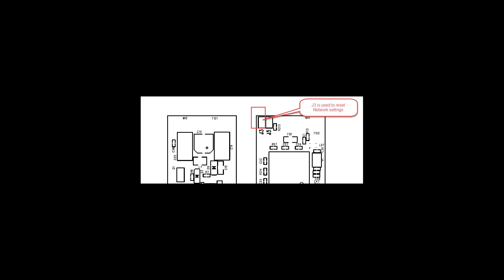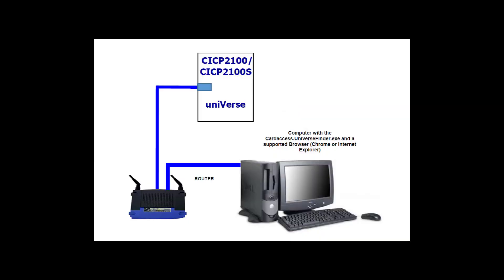After the CICP-2100 and CICP-2100S powers up, you must remove the jumper from J3 after 5 seconds. J3 is the two pins closest to the cutout in the PCB. Please refer to the service and installation manual for the jumper locations. Prior to starting, please take note of the MAC address of the unit — there will be a label on the unit displaying the MAC address.